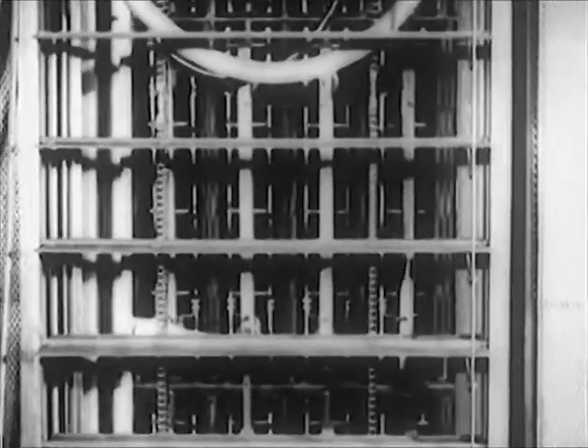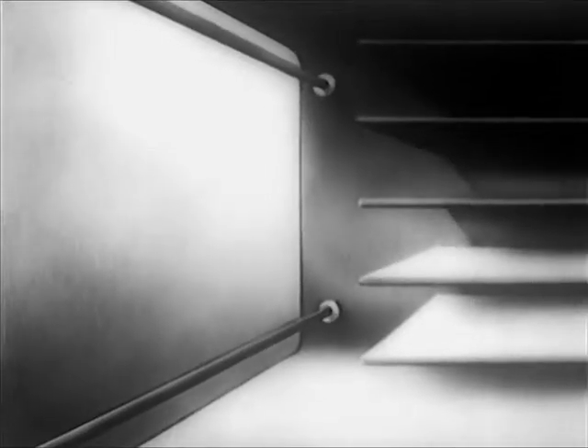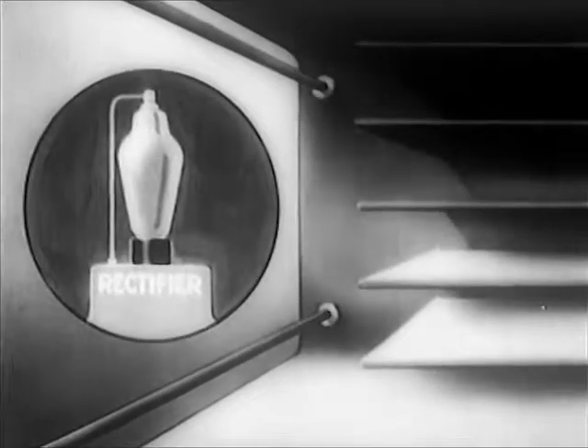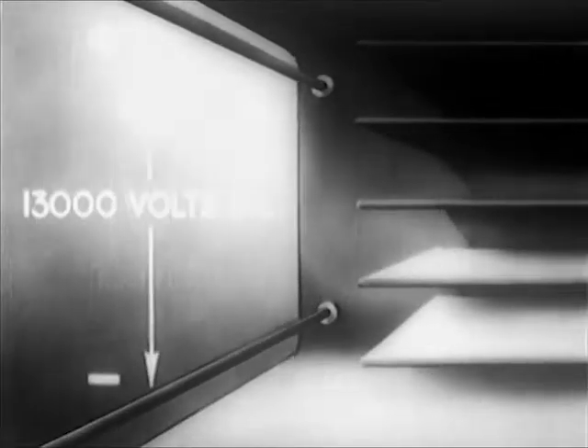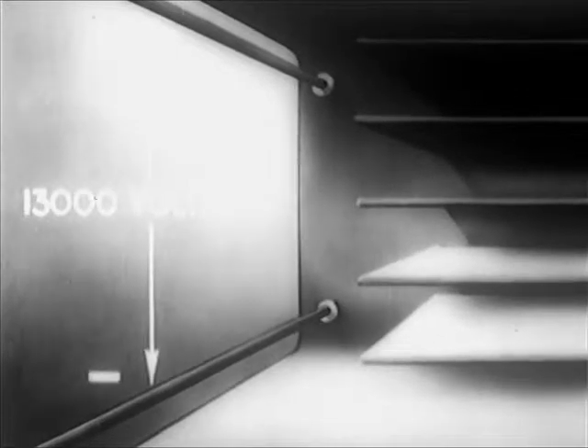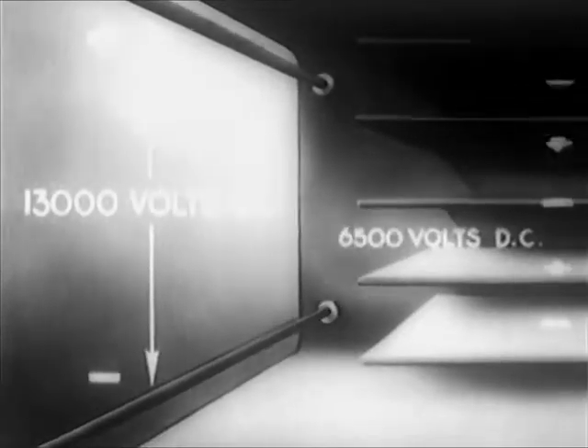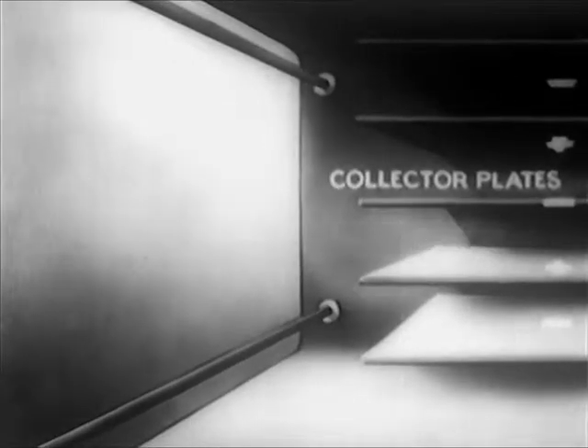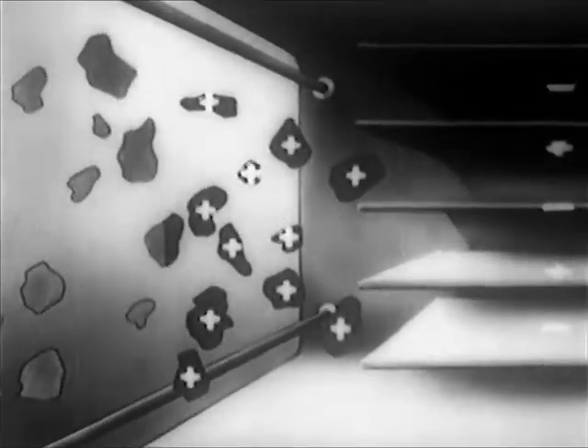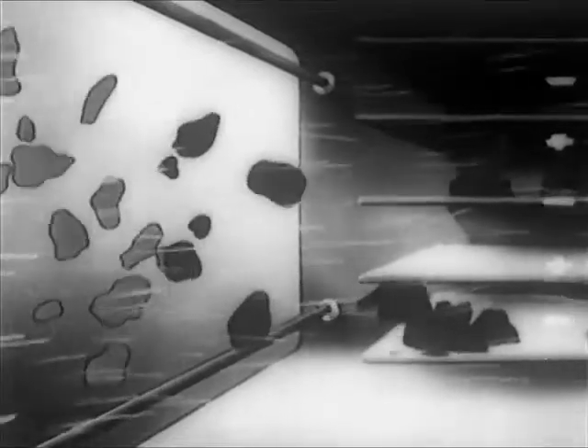Still another example of electronic rectification at work is the precipitron, a device for cleaning air electrostatically. This diagram explains how the precipitron works. The rectifying property of electronic tubes is used to apply a potential of 13,000 volts DC to tungsten wires and 6,500 volts DC to collector plates. As incoming air passes through the field of these wires, each particle of dirt receives a positive electrostatic charge. When the positively charged particle reaches the collector chamber, it's attracted to and deposited on negative plates.